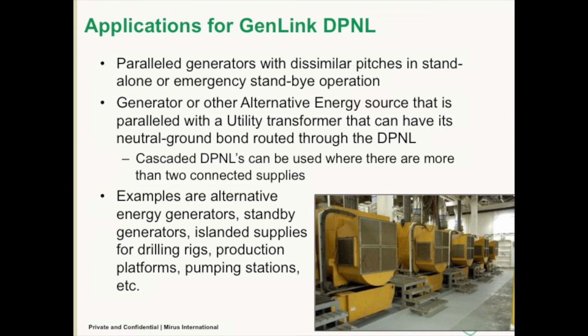There are many applications for the GenLink. If we've got parallel generators with dissimilar pitches in standalone or in emergency standby operation. Generators or other alternative energy sources that are paralleled with a utility transformer. And if we have multiple generator configurations, multiple transformers, we can do cascaded applications for the DPNL. Some examples would be alternative energy generators, standby generators, islanded supplies for drilling rigs, production platforms, pumping stations, etc.